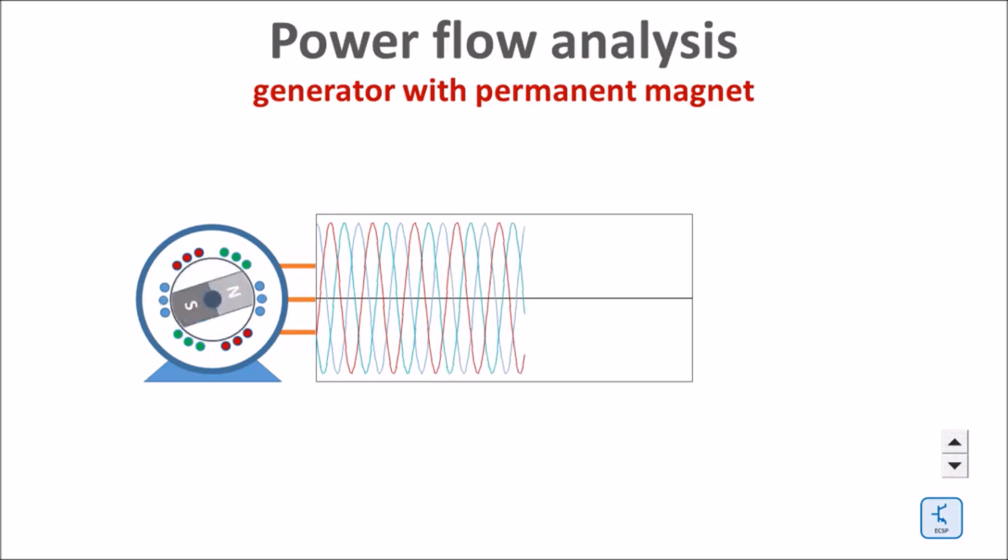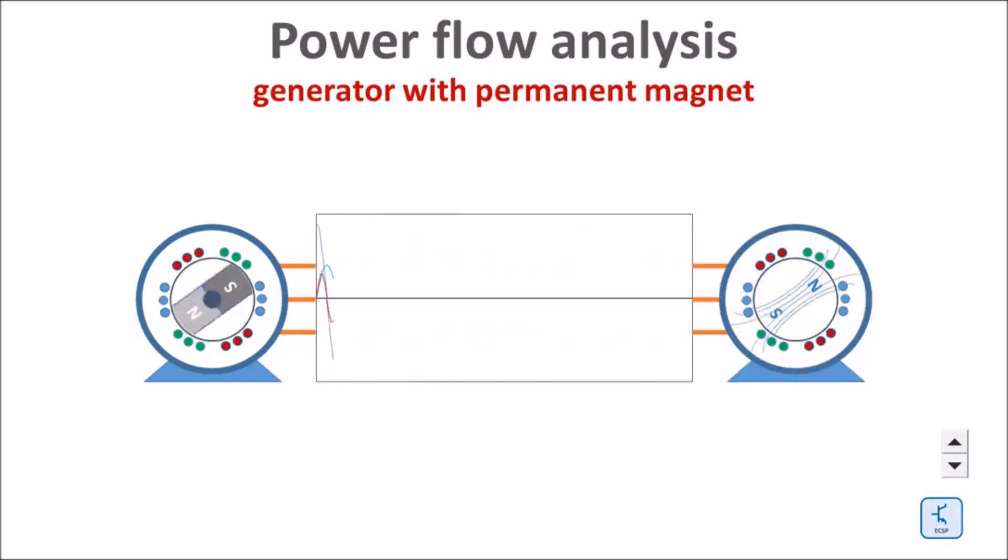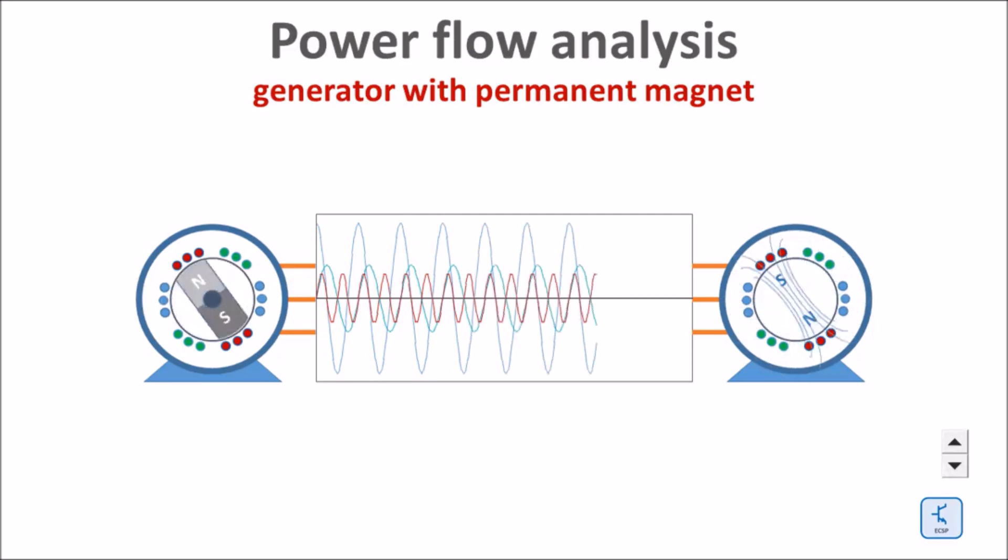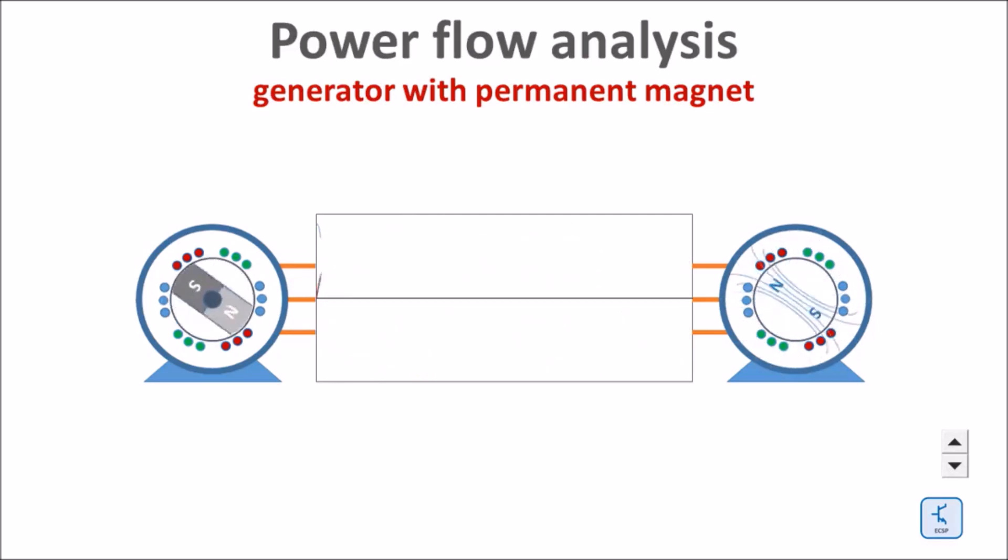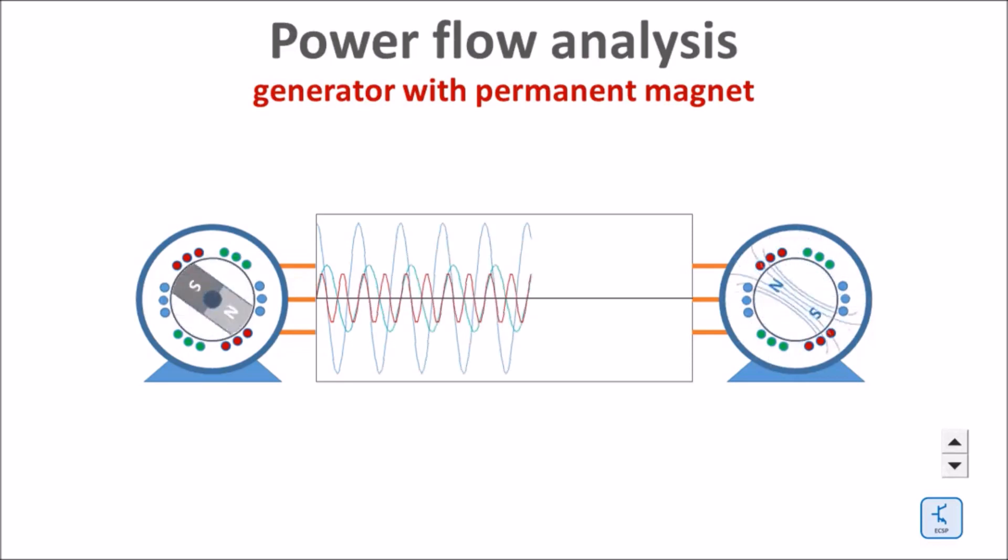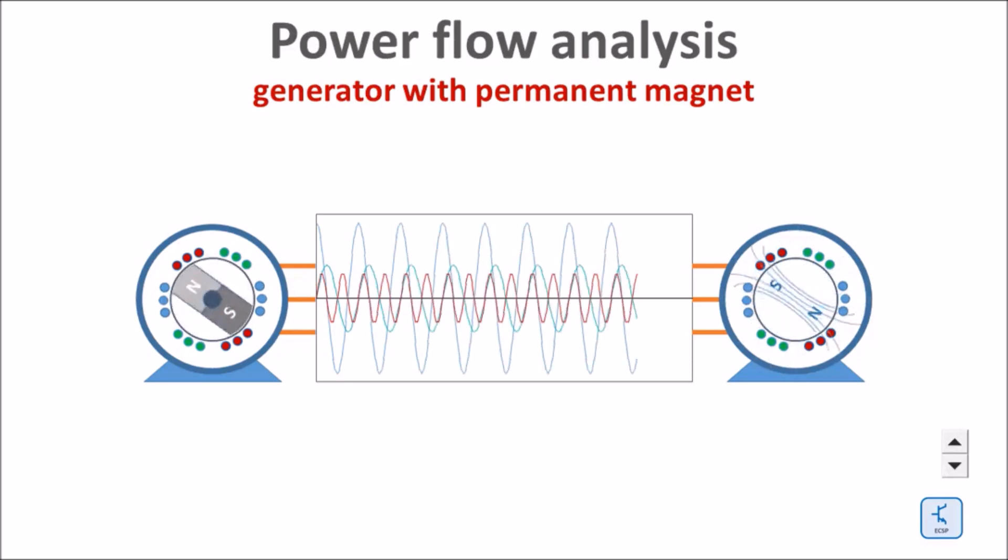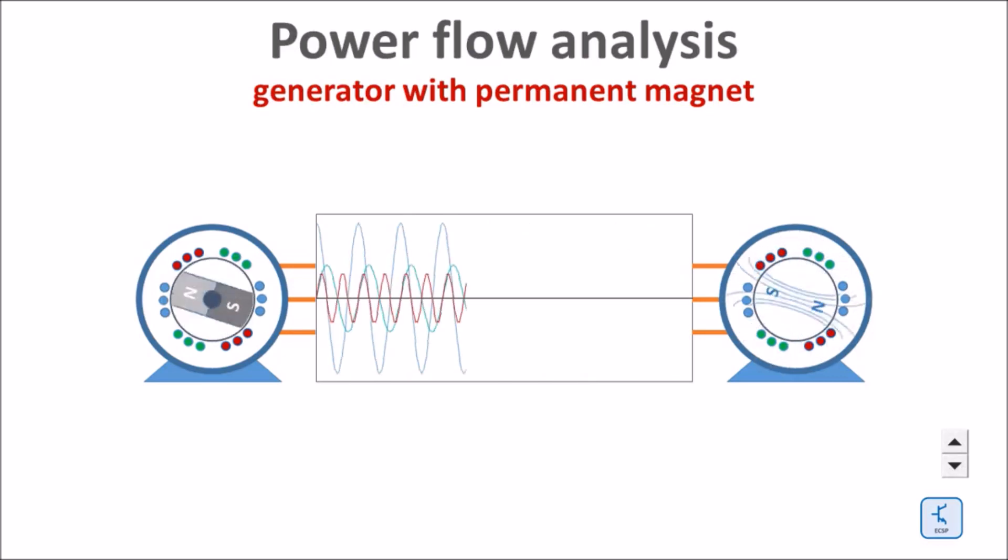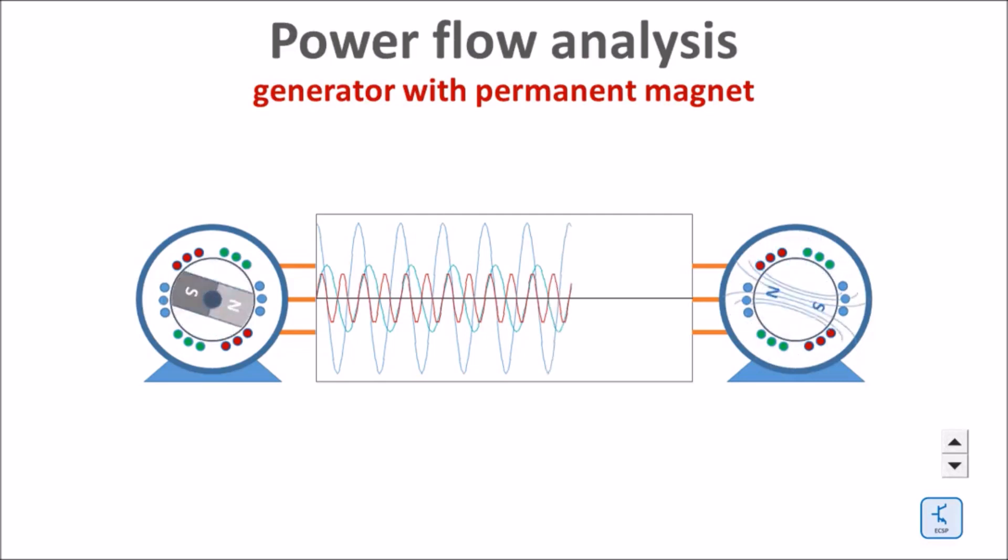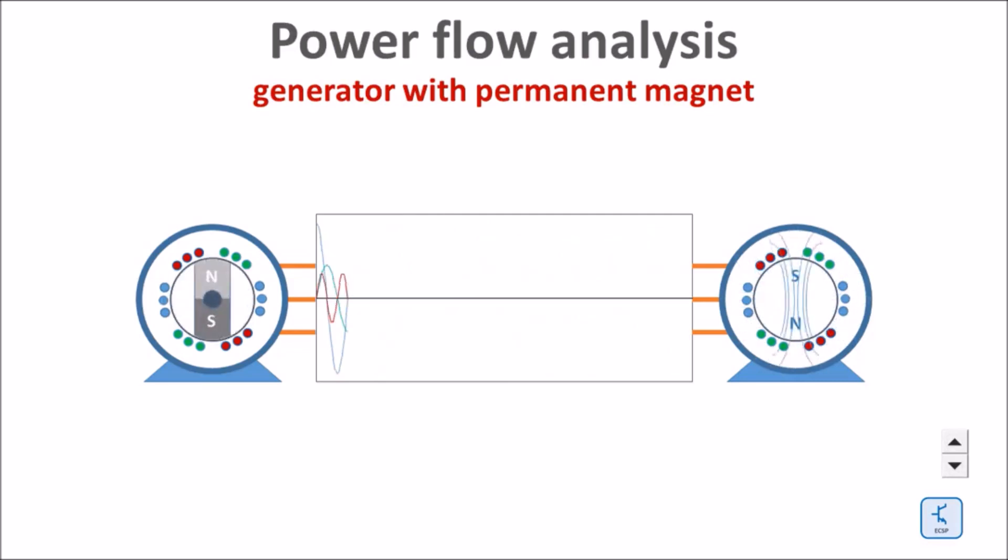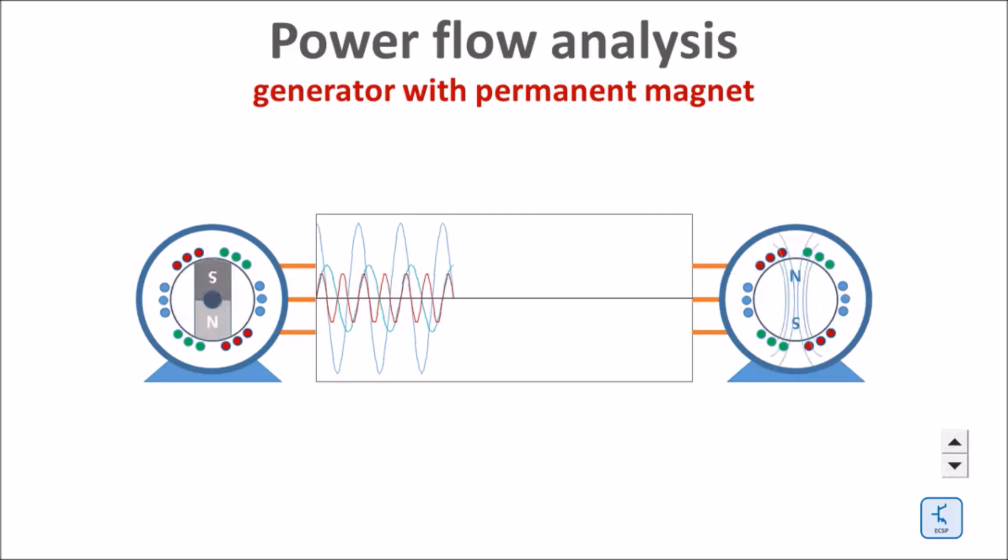Next I connect two synchronous generators to each other. The generator to the right did not yet get a rotor, thus the three phase voltage induced by the fully equipped rotor to the left induces a rotating magnetic field in the stator of the generator on the right side. The magnetic field to the right is 180 degrees phase shifted compared to the source magnet to the left.